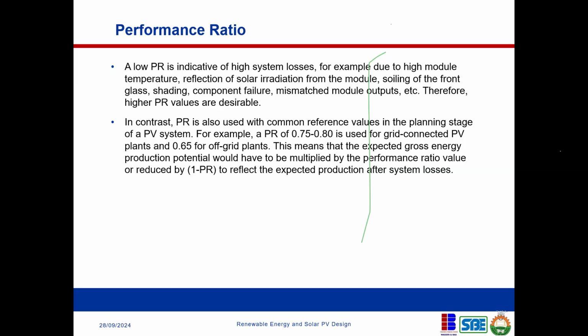It is safe to use something like a 70% performance ratio for Nigeria. If you're doing your design, I mean your initial design, and you want to calculate the energy yield that you could actually get out of this solar PV.